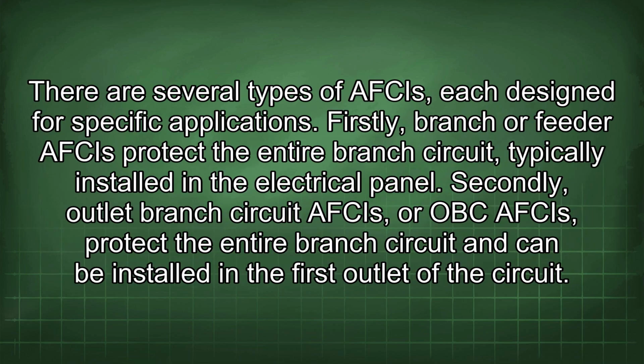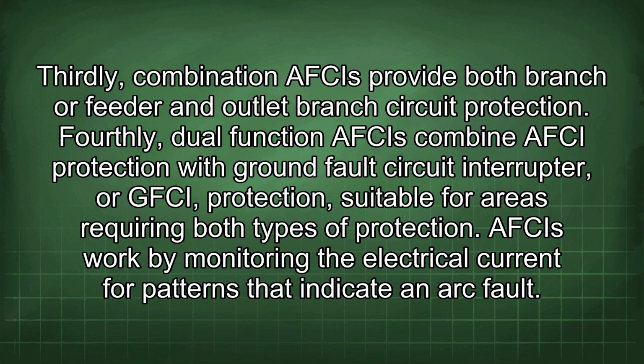There are several types of AFCIs, each designed for specific applications. Firstly, branch or feeder AFCIs protect the entire branch circuit, typically installed in the electrical panel. Secondly, outlet branch circuit AFCIs, or OBC AFCIs, protect the entire branch circuit and can be installed in the first outlet of the circuit. Thirdly, combination AFCIs provide both branch or feeder and outlet branch circuit protection. Fourthly, dual function AFCIs combine AFCI protection with ground fault circuit interrupter, or GFCI, protection, suitable for areas requiring both types of protection.